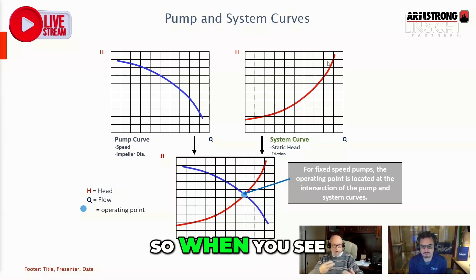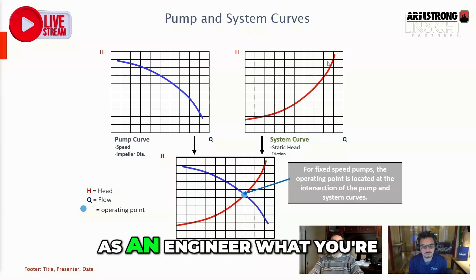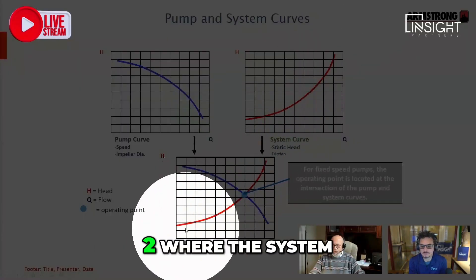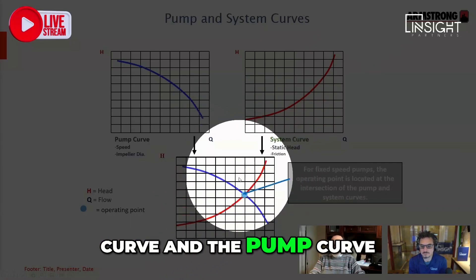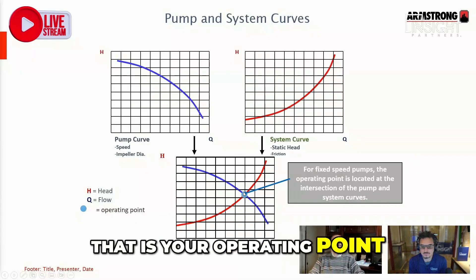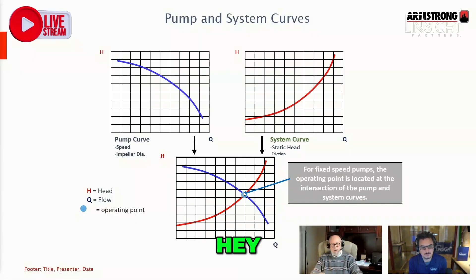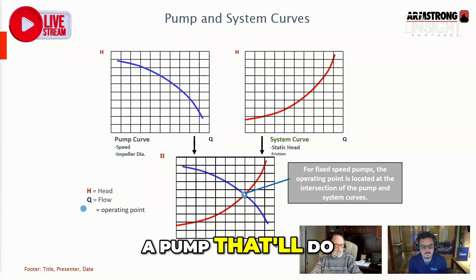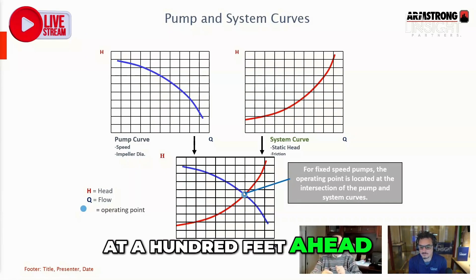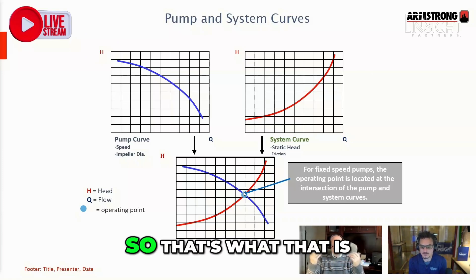So when you see a pump curve, what you're getting is the intersection of the two — where the system curve and the pump curve intersect, that is your operating point. That's the duty point that you've selected, or you've said, 'Hey Mr. Armstrong, I want a pump that'll do 5,000 GPM at 100 feet of head.' And that's where that dot's going to be.